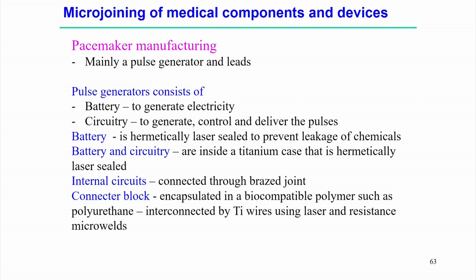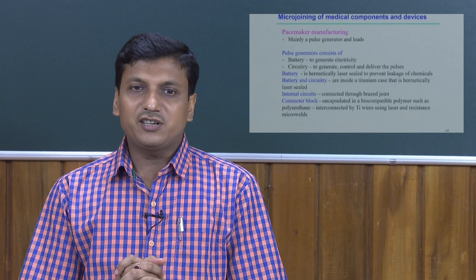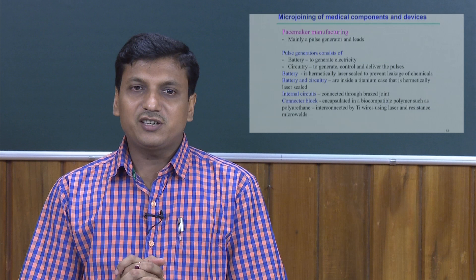The battery is hermetically laser-sealed to prevent any leakage of chemicals. The battery and the circuit board are inside a titanium case that is also hermetically laser-sealed. During sealing, the laser source is applied to seal the materials completely, making a package of the complete pacemaker. The internal circuits are generally connected through the brazing process, and the connector block is sometimes encapsulated in a bio-compatible polymer such as polyurethane, interconnected by titanium wire. Typical welding processes are laser and resistance micro welding.